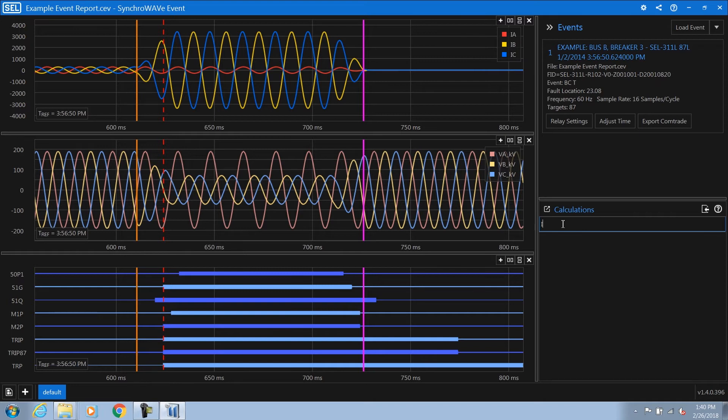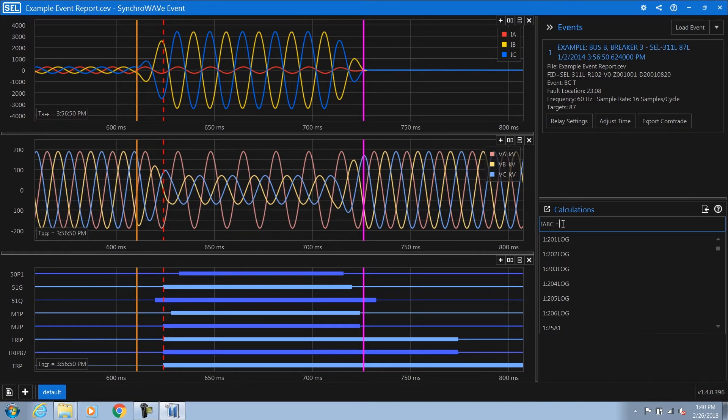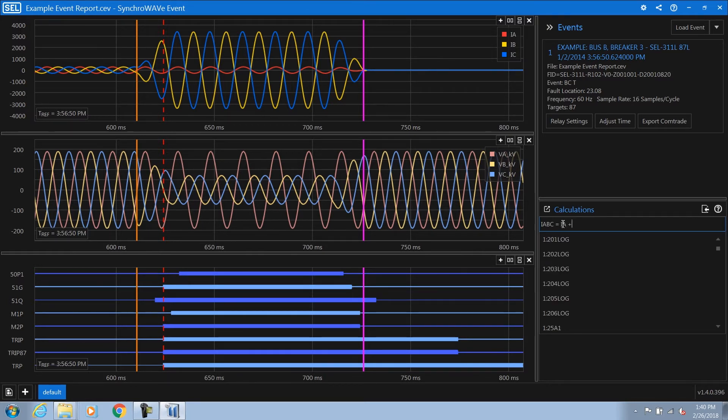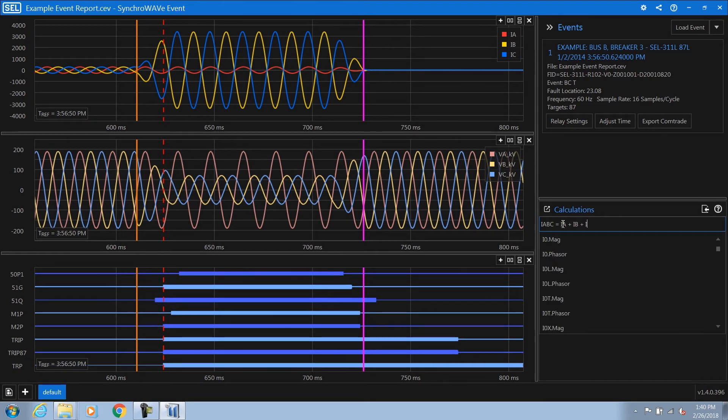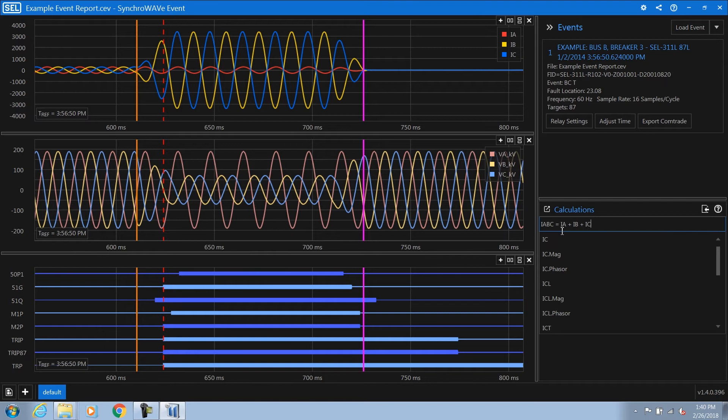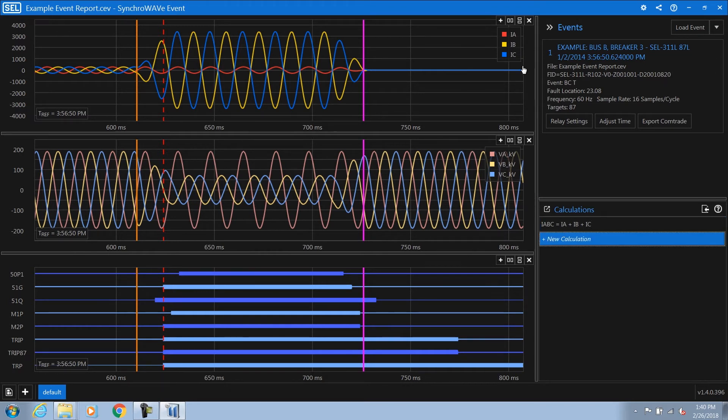So I'm going to declare IABC as my variable, and then I'm going to sum up the phase currents, IA plus IB plus IC. You can also use the autocomplete feature as well. Pressing enter finalizes the equation and then makes it available in your trend chart.